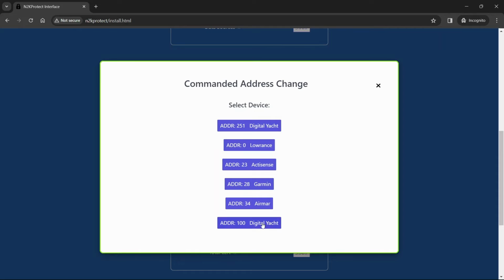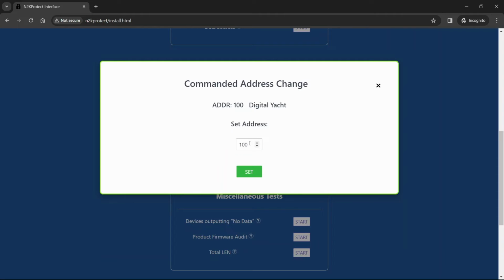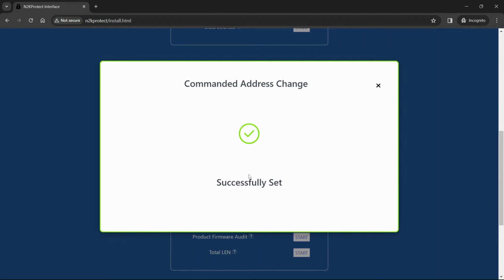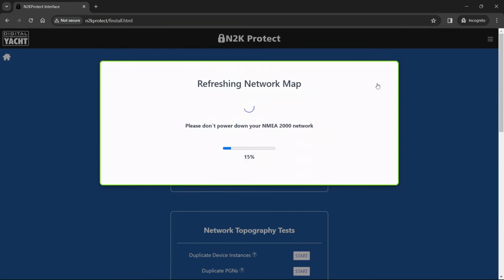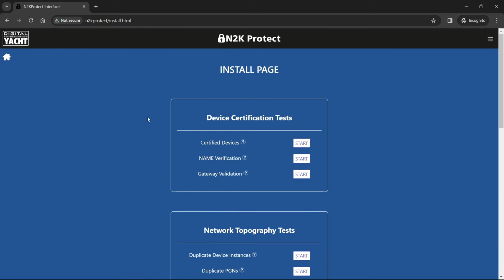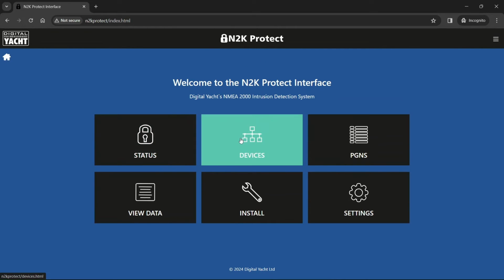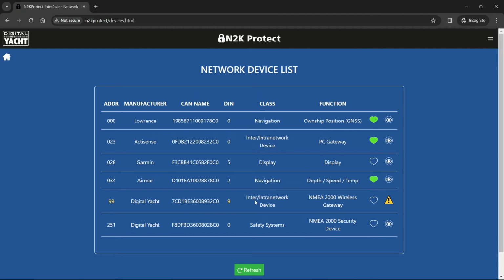We'll go to use that again. It's got a CAN address of 100 at the moment, so we're going to make that 99, and I'll set that. So it's successfully set that. We should get an alarm, which we do, just to warn us that's another change on the network. And we'll go to the devices, and you'll see now that not only has it got a changed device instance, it's got the changed CAN address as well. So again, it's still got this warning sign to show there's a potential problem there.